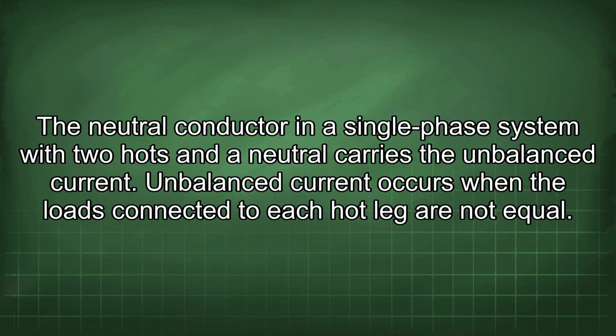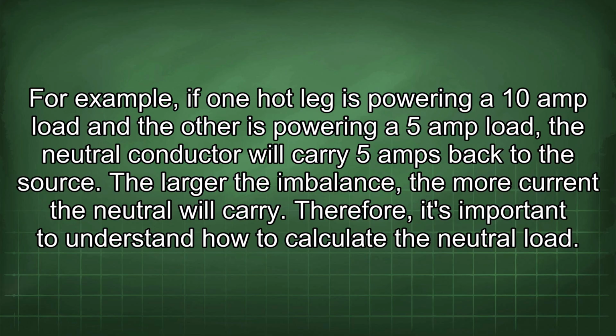The neutral conductor in a single-phase system with 2 hots and a neutral carries the unbalanced current. Unbalanced current occurs when the loads connected to each hot leg are not equal. For example, if one hot leg is powering a 10 amp load and the other is powering a 5 amp load, the neutral conductor will carry 5 amps back to the source. The larger the imbalance, the more current the neutral will carry. Therefore, it's important to understand how to calculate the neutral load.